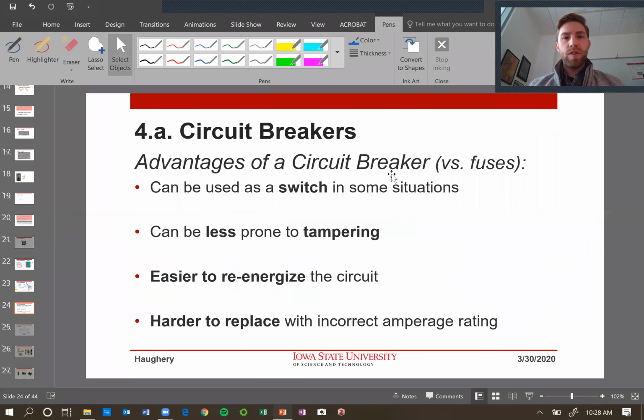Switching over to the advantages and disadvantages of circuit breakers over fuses: a circuit breaker can be used as a switch. So you can use it to turn off the circuit. You can actually lock those out, lockout/tagout. Less prone to tampering, easy to re-energize. You just flip the circuit breaker back on. It's a little bit harder to replace. You have to pull it out, unwire, put it back in, rewire. Whereas a fuse, you can just unscrew and screw back in.